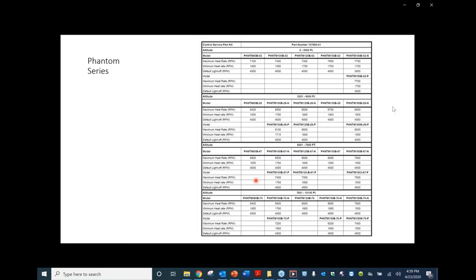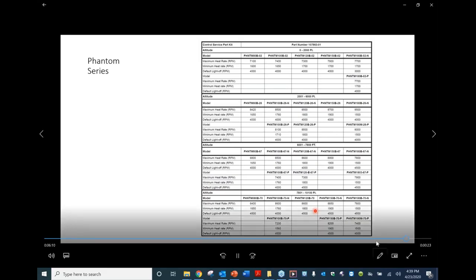The Phantom 80 only has natural, with no propane at altitude. The 100 does have some propane altitudes. The 120 is only good to 6,700 feet. And the 150 goes all the way up, and the 180 will go up if it is an M model. There's that model designation change. Again, all of the LP conversions will be covered in a different training. This is just for setting up the boiler for altitude.